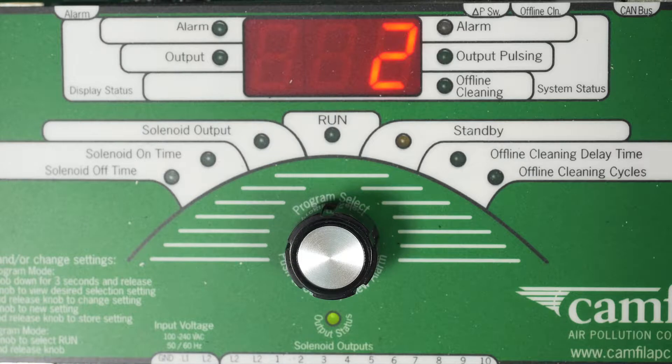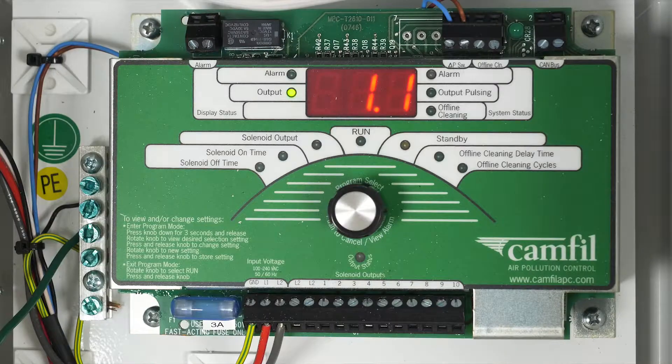Solenoid output: this value sets how many solenoids will be pulsed and is adjustable from 1 up to the maximum number of solenoids available. The number of expansion boards connected to the system on power-up determines the maximum number of solenoids available. On power-up, the controller polls the CAN bus to determine the number of outputs available. This number can be viewed by selecting the output program item.